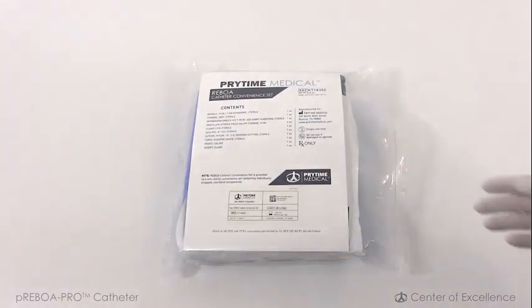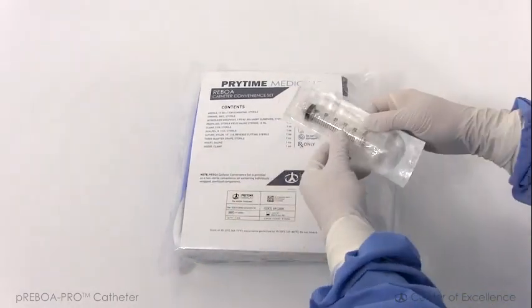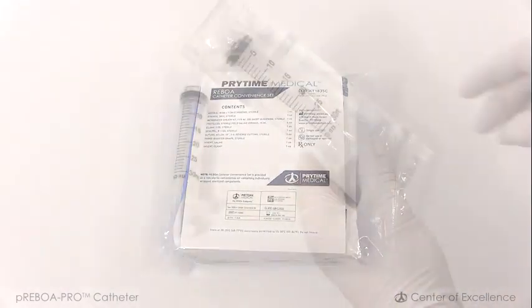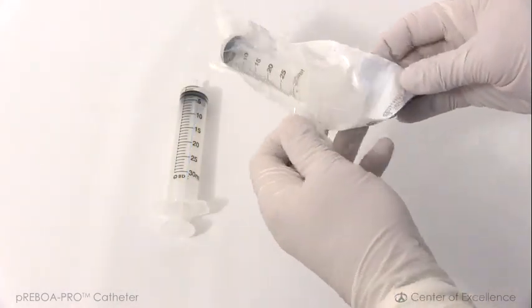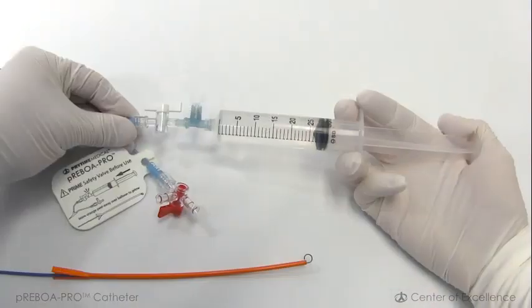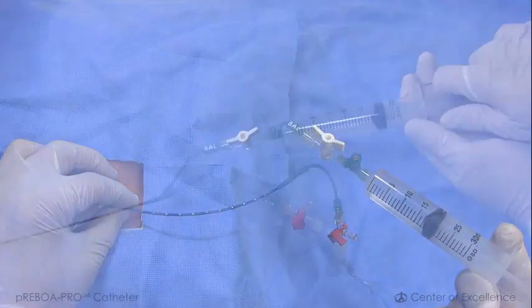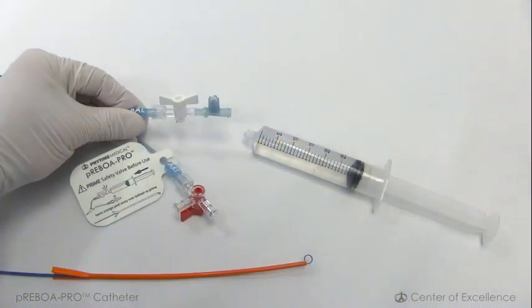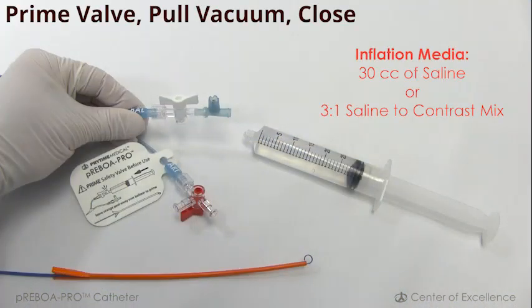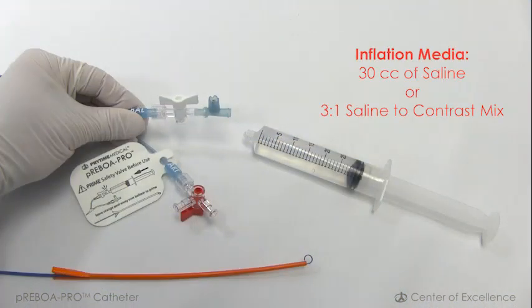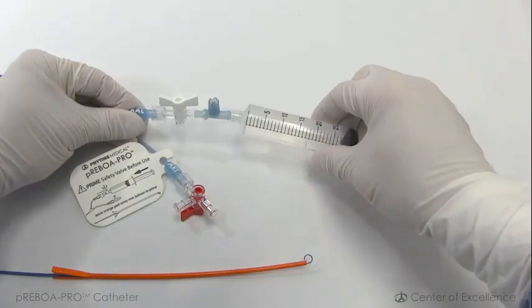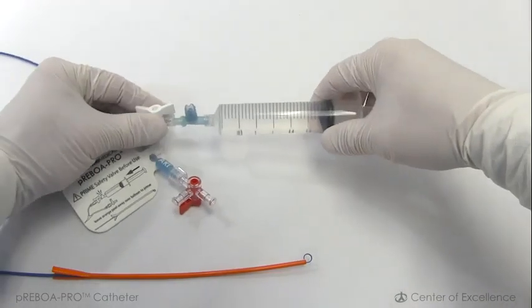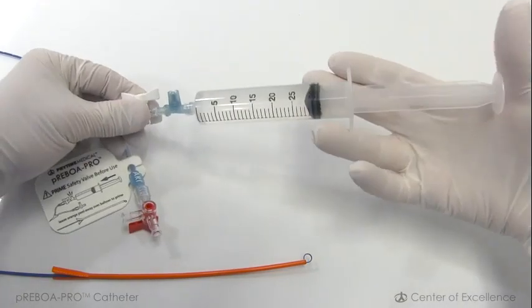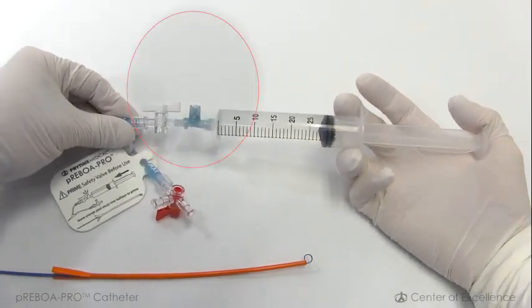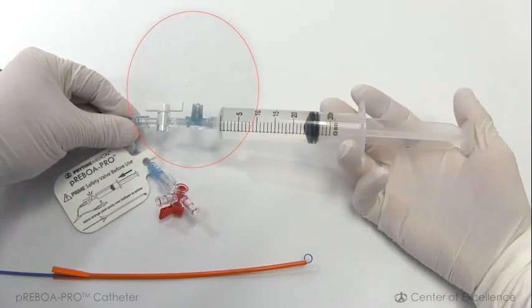With the orange peel-away sheath in place over the balloon, get the 30cc syringe from the pREBOA convenience kit. We recommend that you use a 30cc syringe during the entire pREBOA procedure, from placement to inflation to deflation. Fill the 30cc syringe with 30cc of saline or 3:1 mix of saline to contrast, and attach the syringe to the balloon lumen of the catheter. Flush a small amount of the saline into the balloon lumen until the safety valve opens. Next, pull a vacuum on the syringe plunger and close the stopcock.